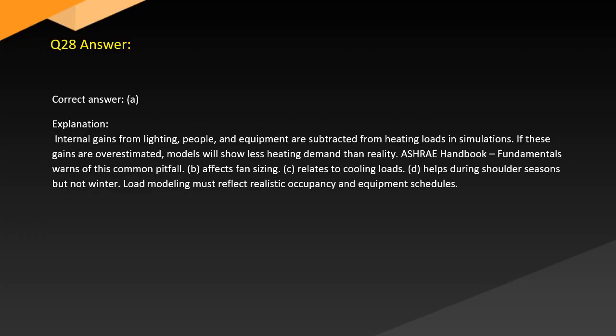Answer. Correct answer: A. Explanation. Internal gains from lighting, people, and equipment are subtracted from heating loads in simulations. If these gains are overestimated, models will show less heating demand than reality. The ASHRAE Handbook Fundamentals warns of this common pitfall. B. Affects fan sizing. C. Relates to cooling loads. D. Helps during shoulder seasons but not winter. Load modeling must reflect realistic occupancy and equipment schedules.